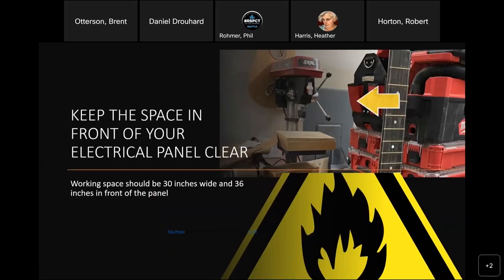Working space matters. In this picture, you can see somebody has a panel in the background—that's what the yellow arrow is pointing to—behind a drill press and a whole bunch of tools. The working space rules for electrical panels in a home are 30 inches wide and 36 inches clear in front of the panel. If this person had an emergency and had to get to a circuit breaker, time would be lost, and possibly someone could be injured or a fire could spread. So keep this space clear.